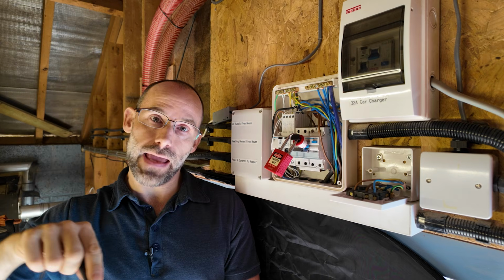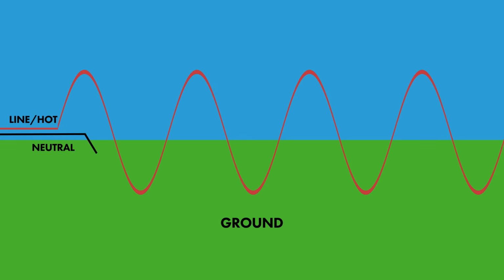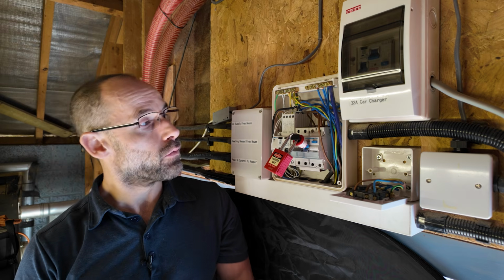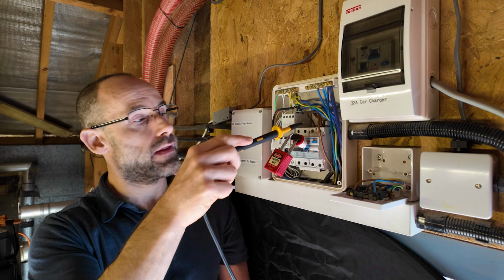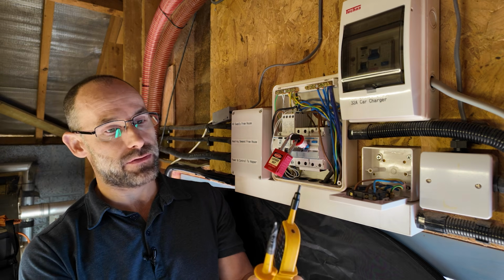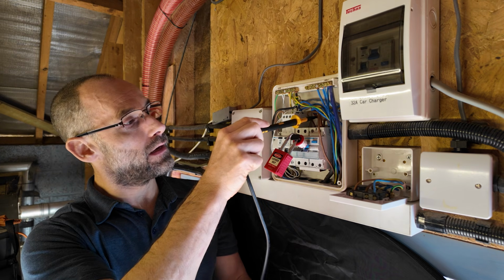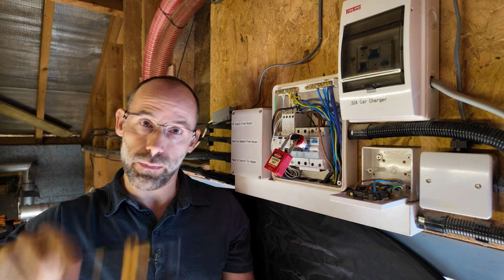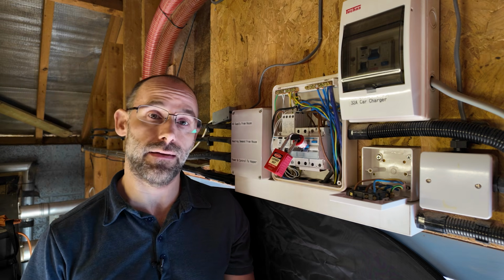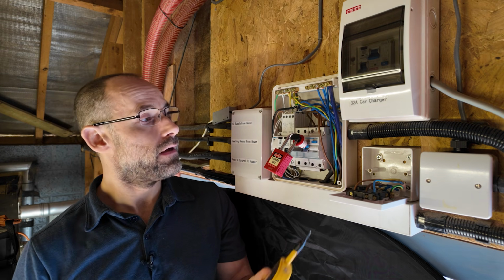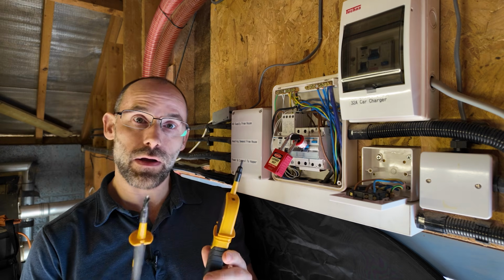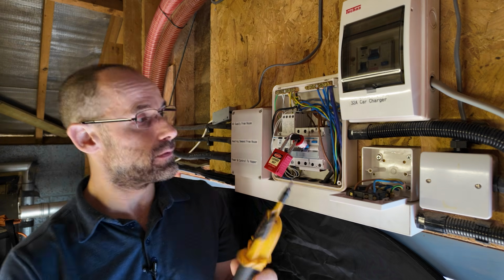Now that it's AC, alternating current, whether it's 110, 120, 240, 230, whatever, you're getting an oscillation around the 0 voltage point, the neutral. So the neutral provides a reference point, and then you get up and down. That's what alternating current means. So it goes positive, negative, positive, negative. So what does it mean to check the polarity of this? I can't just put a meter with a plus and minus probe on my line and neutral because it goes plus minus, plus minus, in our case 50 times a second, over in the US more like 60. So we still, though, can check that the right things are correct. Now, let me just show you how.